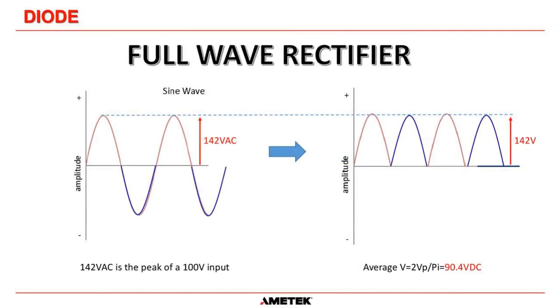So let's say it was 100 volts - maybe a substation far away from the main connection and volt drops in the cable, whatever reason, the 120 volts in this situation was 100 volts. Well, that makes the peak of the sine wave now 142 volts. And if we use our equation, we've now gone to 90.4 volts DC. So the DC changes with changes in the AC.